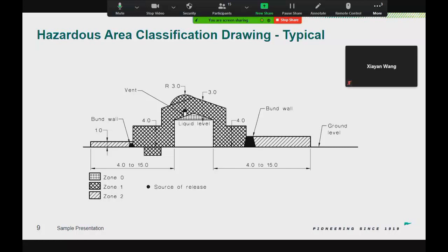This might be a little bit of a silly question, but would something like ingress protection cover zone protection in any way, or would it be considered separate for dust and gas? Sorry, can you repeat that? Would something like an ingress protection rating cover the zone classification, or would it be considered separate too? The answer is no, in short, it doesn't, because ingress is only good while the piece of equipment is closed. Once you open it, what happens? What happens if the seal is failed? You cannot take that risk.